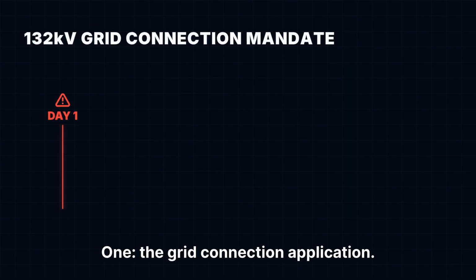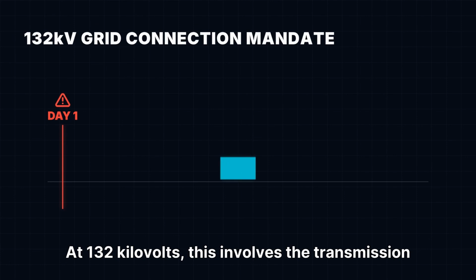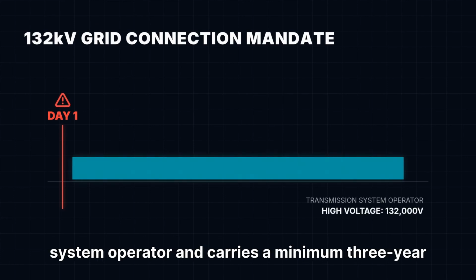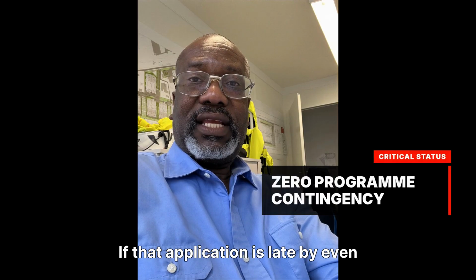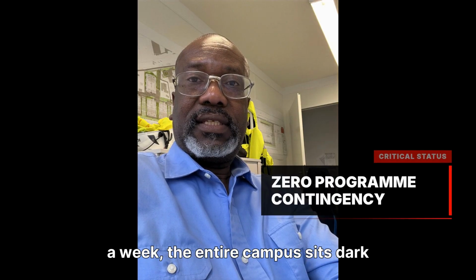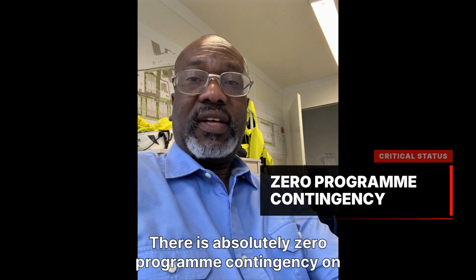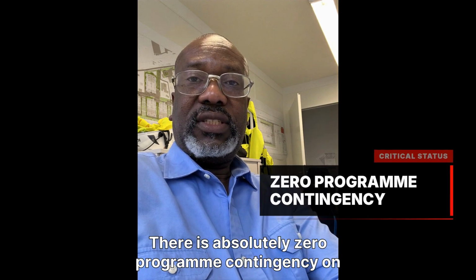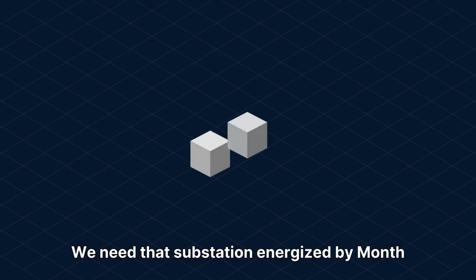The most critical milestone happens on day 1, the grid connection application. At 132 kilovolts, this involves the transmission system operator and carries a minimum 3-year lead time. If that application is late by even a week, the entire campus sits dark while the equipment waits. There is absolutely zero program contingency on this one single item. We need that substation energized by month 18.